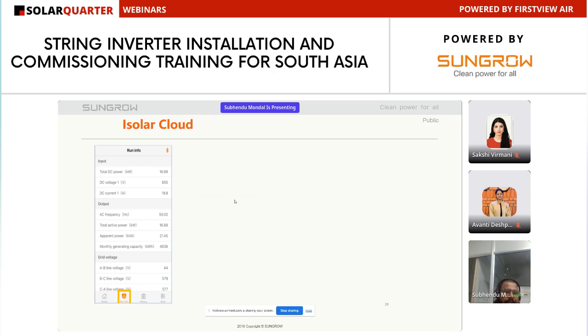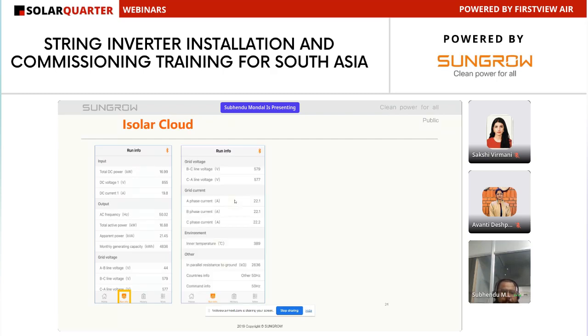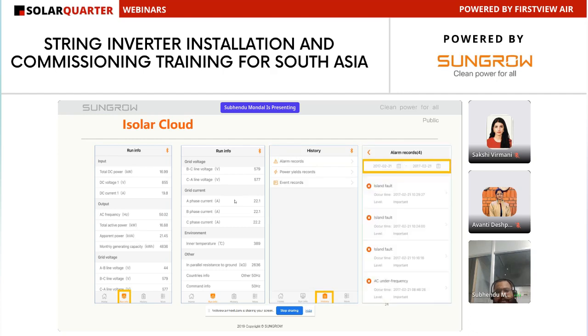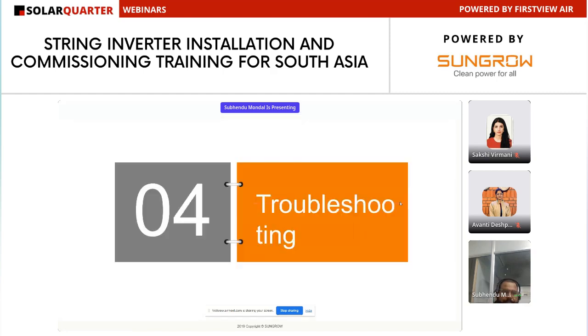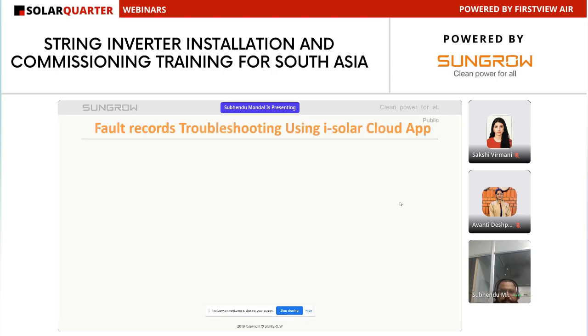You can see the DC voltage and total active power, apparent power, monthly generation capacity, phase to phase voltage, then grid current, temperature, and for the history option we can check the fault record. If any fault occurs, we can check from the alarm records and find what fault occurred. We have to troubleshoot accordingly. So the next part is troubleshooting: fault records and troubleshooting using the iSolar Cloud app.